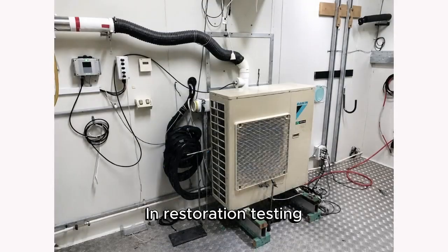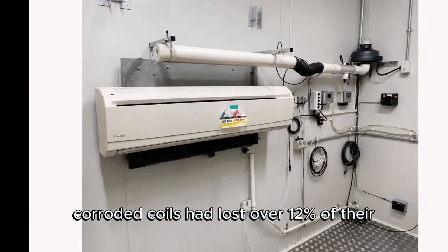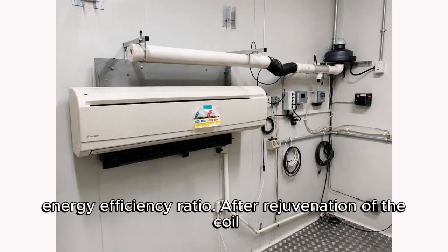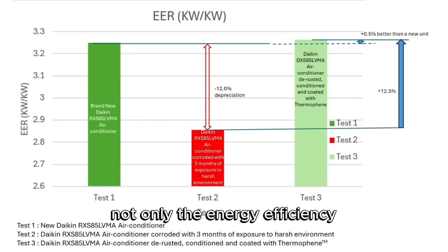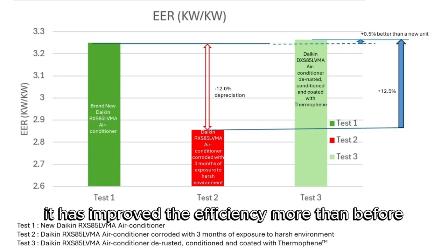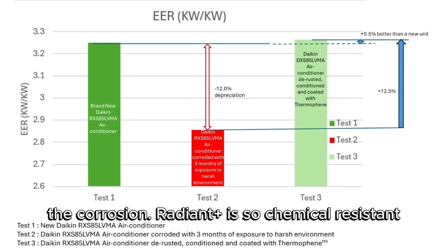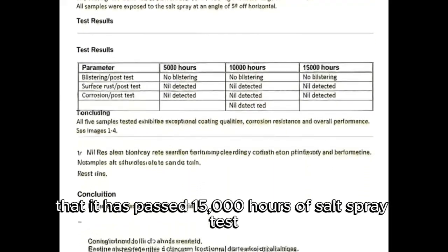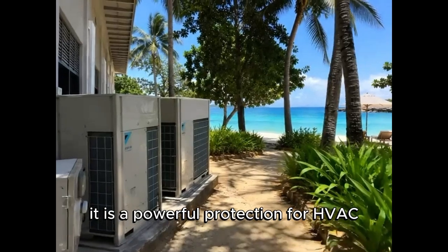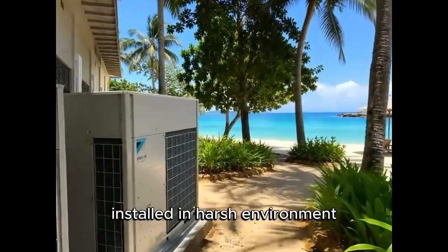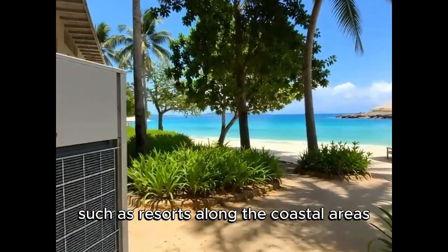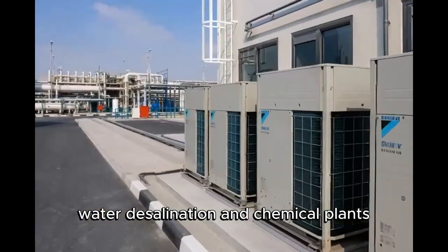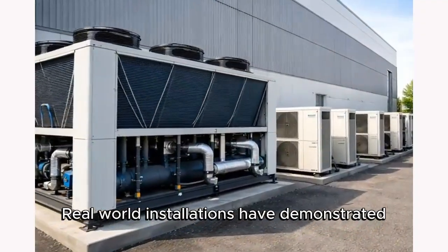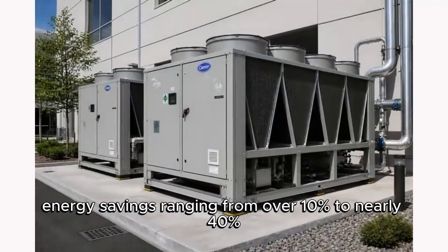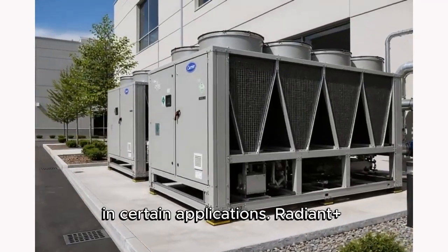In restoration testing, corroded coils had lost over 12% of their energy efficiency ratio. After rejuvenation of the coil, not only was the energy efficiency loss totally restored, it improved the efficiency more than before the corrosion. Radiant Plus is so chemical resistant that it has passed 15,000 hours of salt spray test. It is a powerful protection for HVAC installed in harsh environments such as resorts along the coastal areas, water desalination, and chemical plants. Real-world installations have demonstrated energy savings ranging from over 10% to nearly 40% in certain applications.